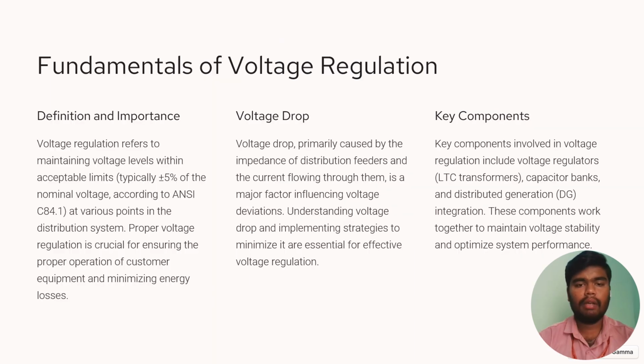In the second slide, fundamentals of voltage regulation. Definition and importance: voltage regulation refers to maintaining voltage levels within acceptable limits, typically plus or minus 5% of the nominal voltage according to ANSI C84.1, at various points in the distribution system. Proper voltage regulation is crucial for ensuring proper operation of customer equipment and minimizing energy losses.